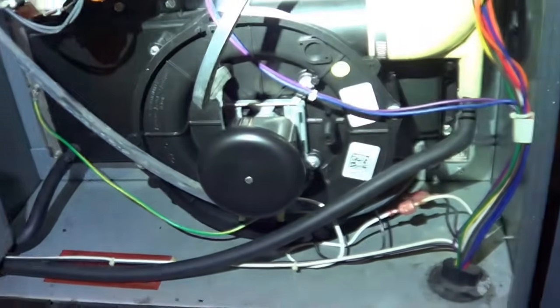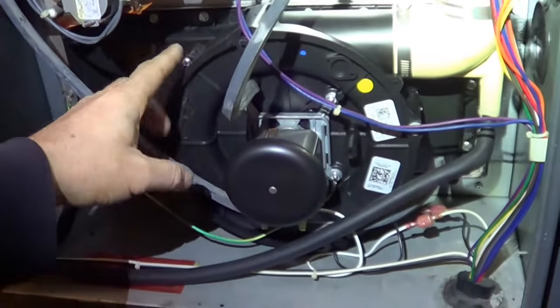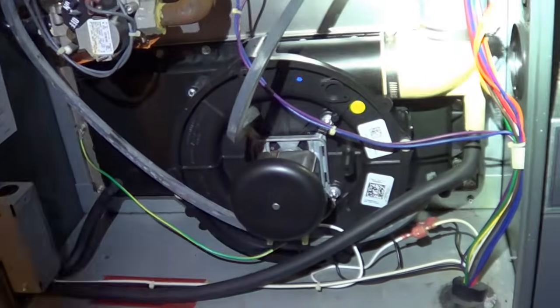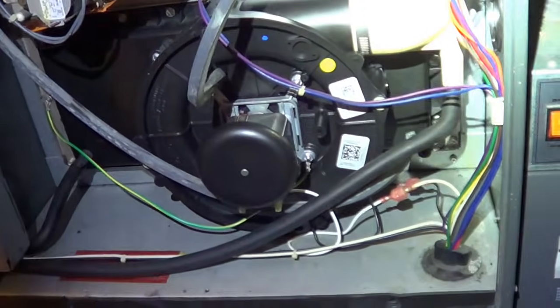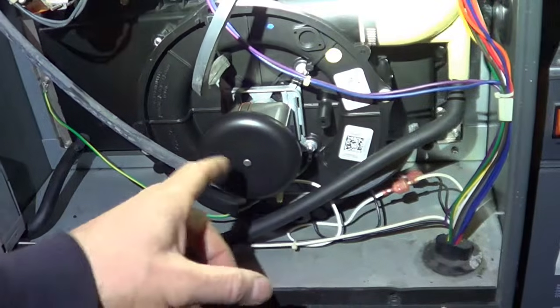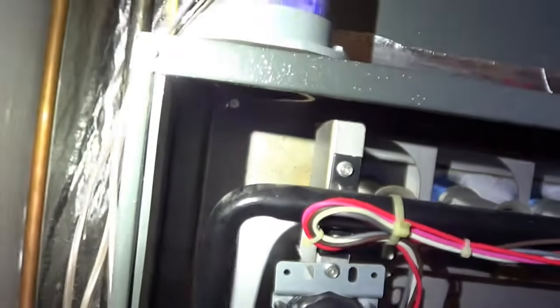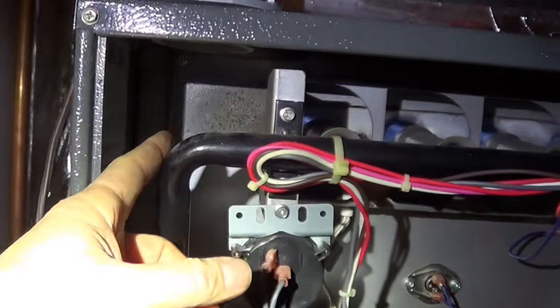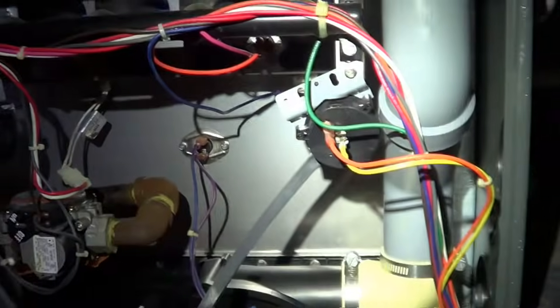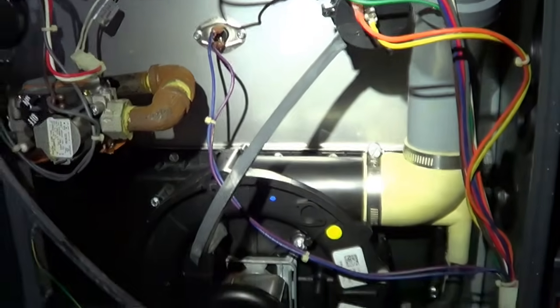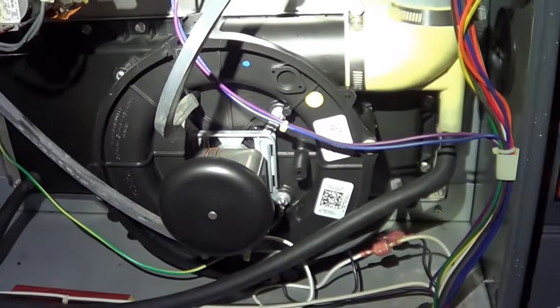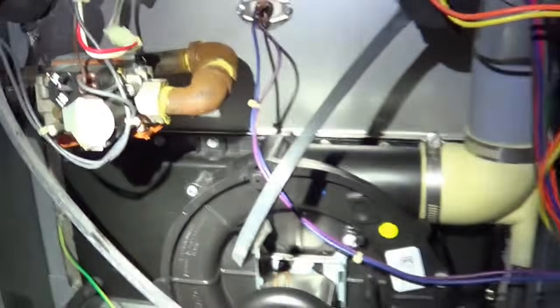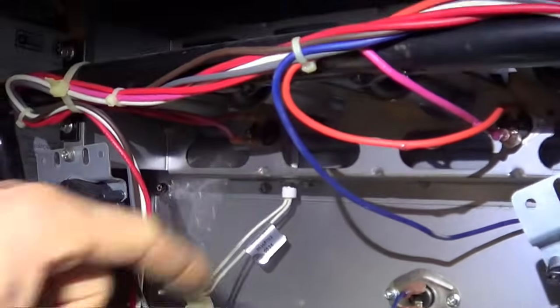I have a furnace here where this is a callback. Originally, this exhaust motor started going bad. The bearings were going bad, so it started losing RPMs, and then we were getting some flame rollout, which you can see right there on the firewall, the soot on the side, and a general just stink on the exhaust. So I swapped out the fan, which was bad, but about a month later we're getting trips on the flame rollout switch.